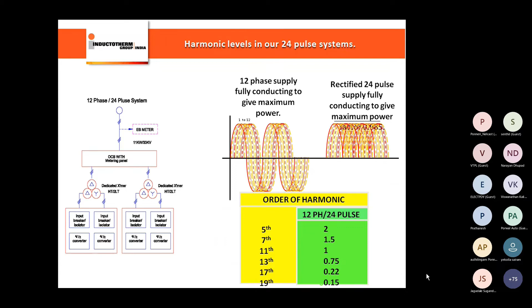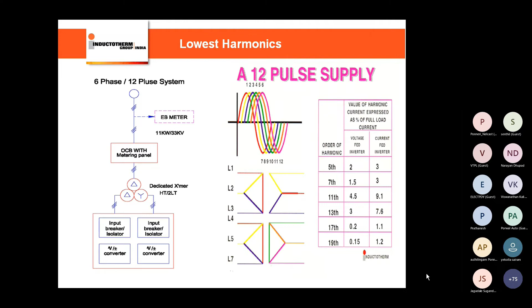Coming to the 12 pulse systems, the harmonics are about 7 to 7.5%, or near 8%. Still, with our 12 pulse designs, our harmonics are well within the TANGEDCO norms or on the border. So Inductotherm provides solutions to mitigate the harmonics in tune with the TANGEDCO norms. We have been consistently doing this for the last 6 to 7 years. For all our latest power supplies from 250 kilowatts or 175 kilowatts onwards, we can supply 12 pulse and 24 pulse designs.